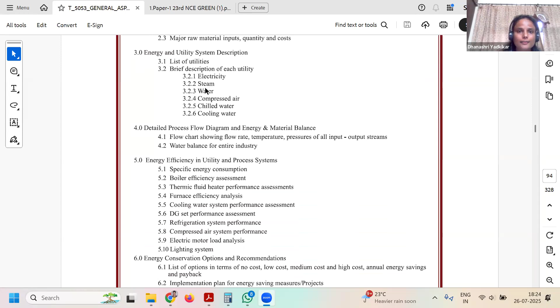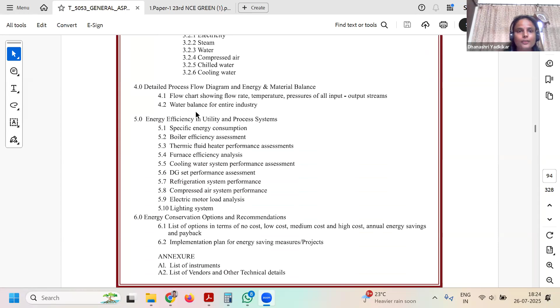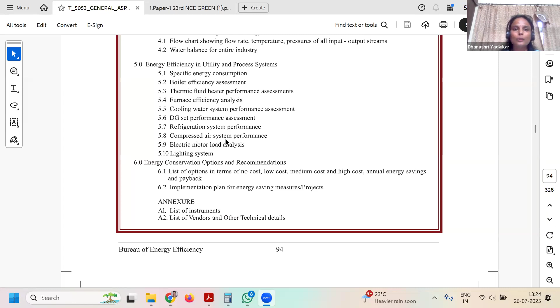A brief description of each utility, that means electricity, steam, water, compressed air, chilled water, cooling tower. Then detailed process flow and energy and material balance, flow chart showing the flow rate and temperatures. Then energy efficiency in utility and process systems. Specific energy consumption is very important. Boiler, if the facility has a boiler, then boiler efficiency assessment, thermic fluid heater performance assessment, furnace, cooling tower, DG sets, AC, refrigeration, HVAC systems, compressed air, electric motor load analysis, and lighting system. The last one is the lighting.